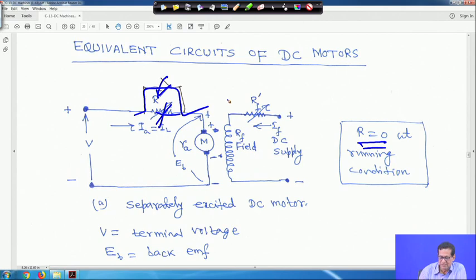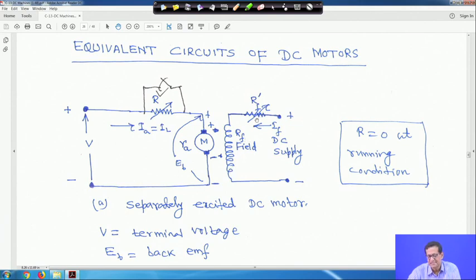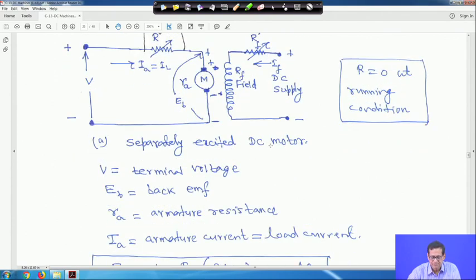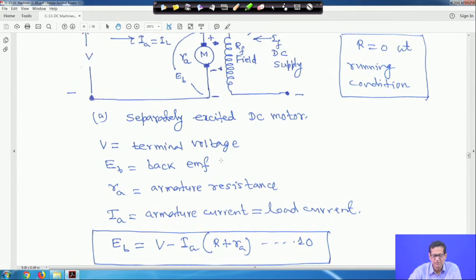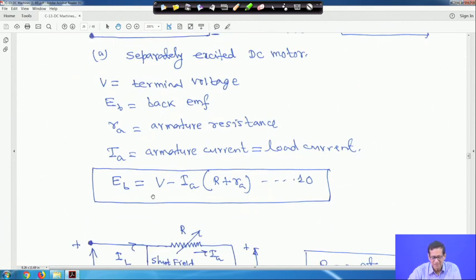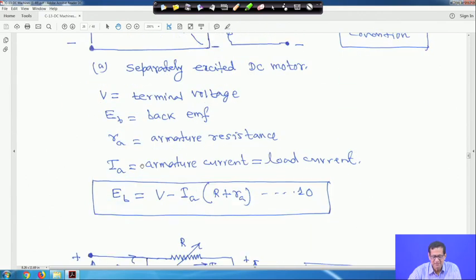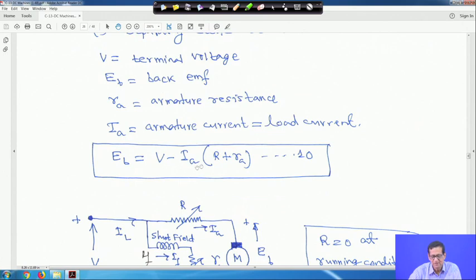This is the separately excited DC motor: V is the terminal voltage, Eb is the back EMF. RF is the field resistance and RF' is the additional field resistance inserted. Applying KVL: EV = V − Ia·(R + Ra). At running condition R = 0, so EV = V − Ia·Ra.